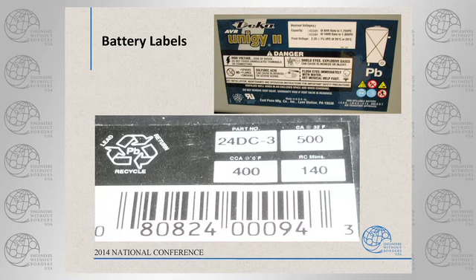Okay, state of charge. What's the approximate percent of the residual capacity left in the battery? This is a typical chart I grabbed from one manufacturer. Do not apply this to any other battery without the manufacturer's permission, because they're all different. Functional life on a battery is considered when the battery can no longer provide more than 80% of its initial rating. So now you go, well, if I design my project right, I can use that battery when it's below 80% of its original capacity. And so you might have a longer number of cycles, a longer number of life based on how you design the system. But when they're defining the expected number of cycles, it's based on this. When the battery only has 80% of its original rated capacity left.